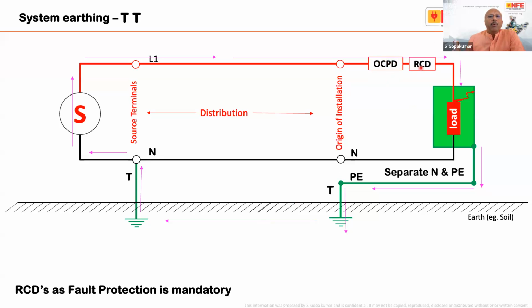So what should we do? We should use an RCD as a fault protective measure. The rated current of the fault protective measure, 30 milliampere or 300 milliampere, is actually a point of discussion. But if you look at the codal requirement, IS 3043, it requires a 30 milliampere RCD as a fault protective measure. This actually makes the system difficult. You cannot install a 30 milliampere RCD on every electronic equipment because it creates nuisance tripping. So this is about the TT system.